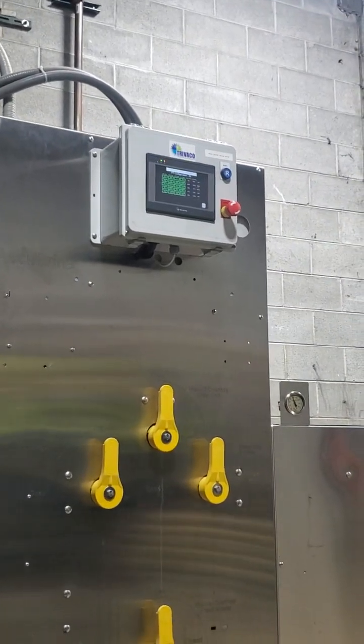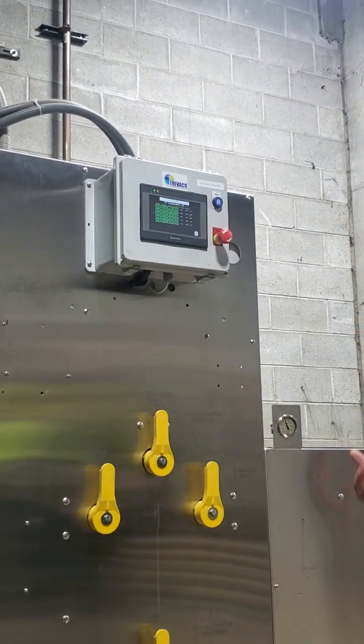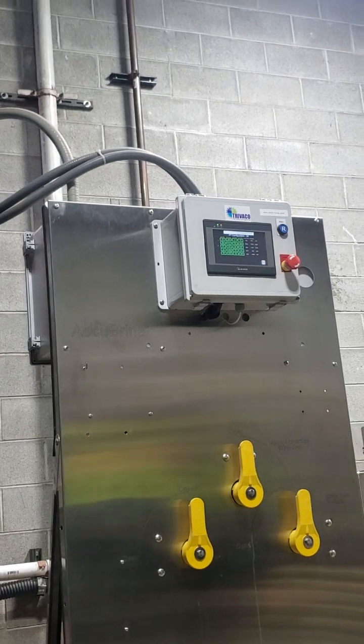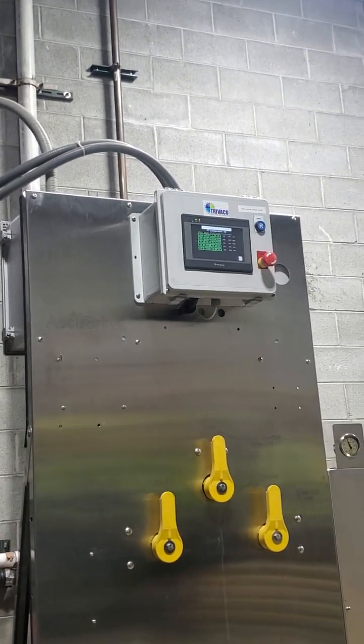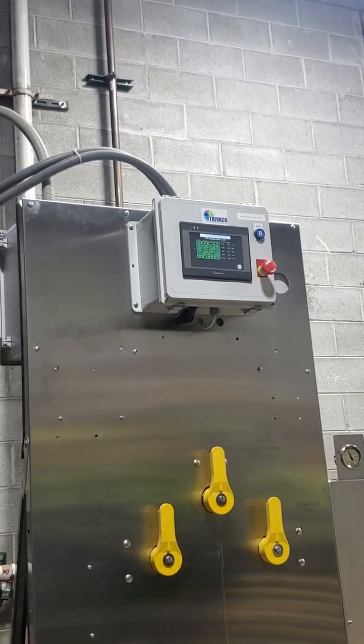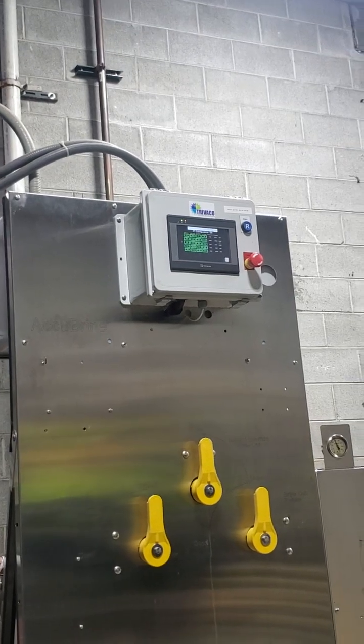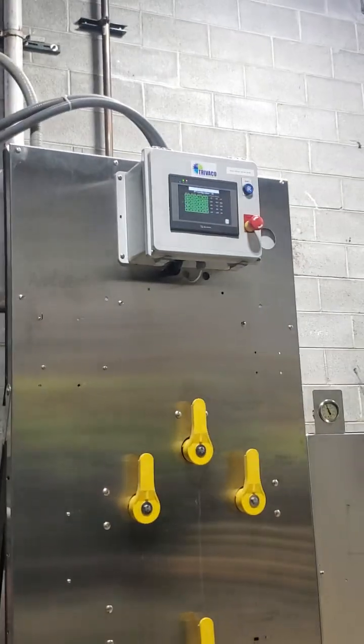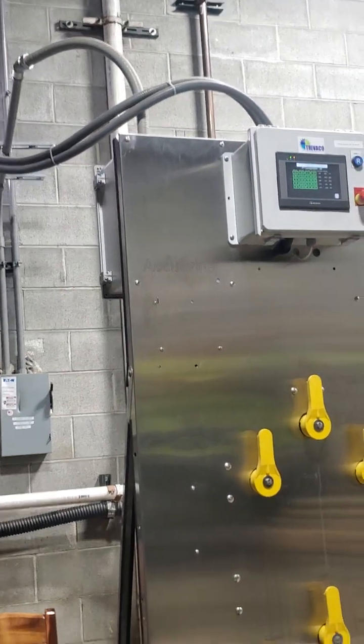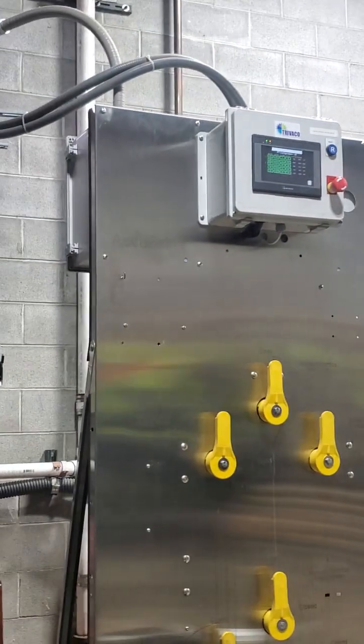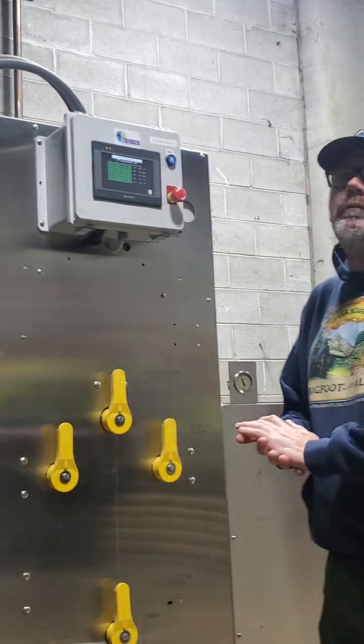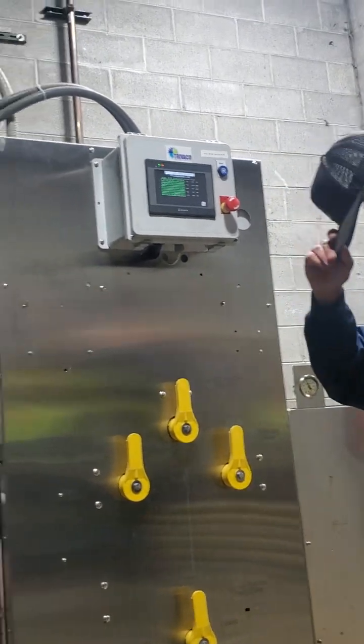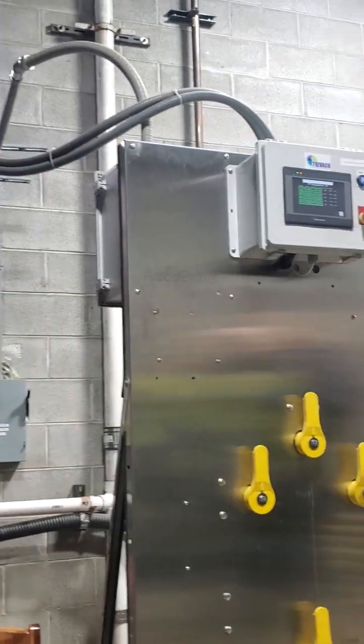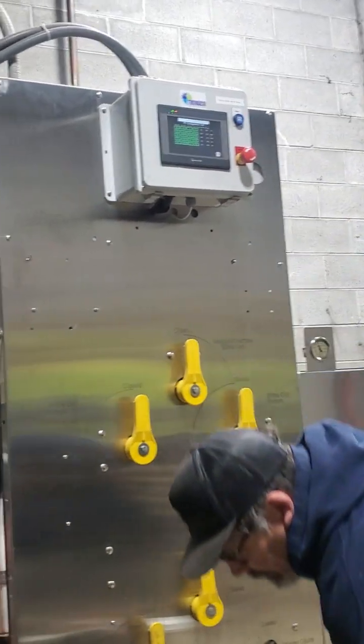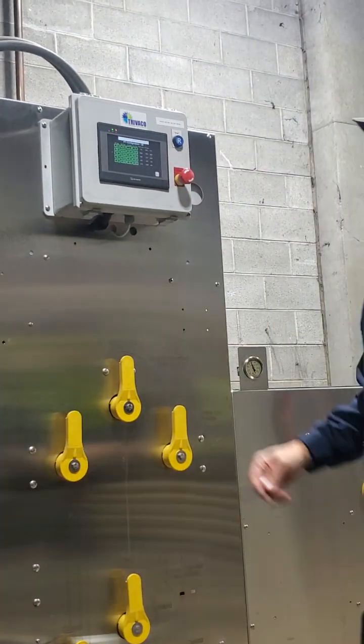Is this pump strong enough to pull those tanks dry? Yeah, sure, but what happens is you end up with air in it, and the PT will say, hey, you're getting low. That's the only safety feature there is. You have to physically look at the PT and the tanks, or look at the tank farm. The pump itself starts sucking in air, it's not going to turn off by itself. It'll just keep going, there's no safety feature for that.